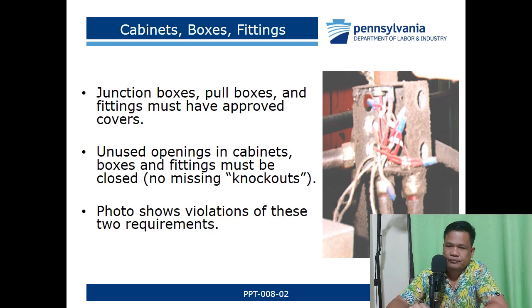Junction boxes, pull boxes, and fittings must have approved covers. If you look at this box, it no longer has a cover. Unused openings in cabinets, boxes, and fittings must be closed, with no missing knockouts. This photo is a violation. Junction boxes need approved covers. This part is called the junction, and this covering part is what you call the junction box. It needs a cover — it's very dangerous without one.